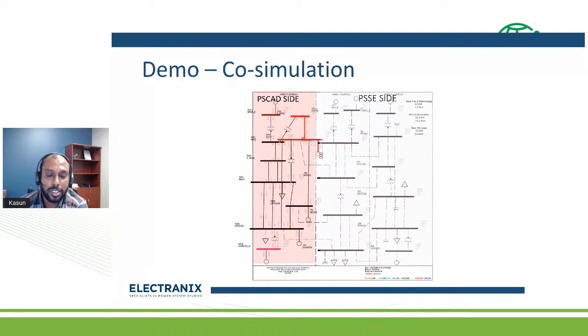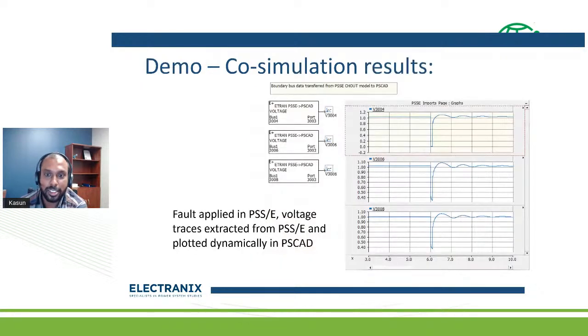This is a demonstration of co-simulation: PSCAD on one side and PSS/E on the other, with a network disturbance applied on the PSS/E side. We bring all the network quantities and channels we need to see from PSS/E to the PSCAD side to analyze the phenomena. Co-simulation is common for low frequency phenomena like SSR, or wide area protection schemes, or full-country scenarios where we keep certain areas in PSCAD and the rest of the country in PSS/E, PSD, PowerFactory, or other software tools.